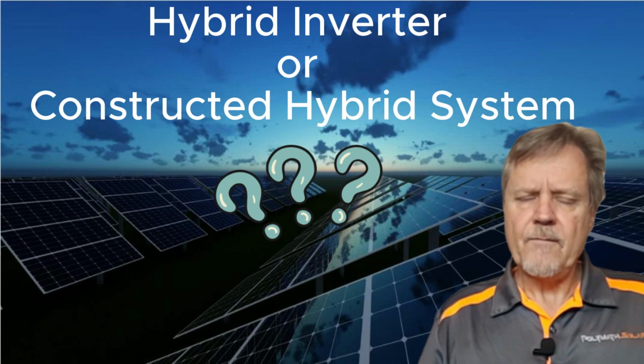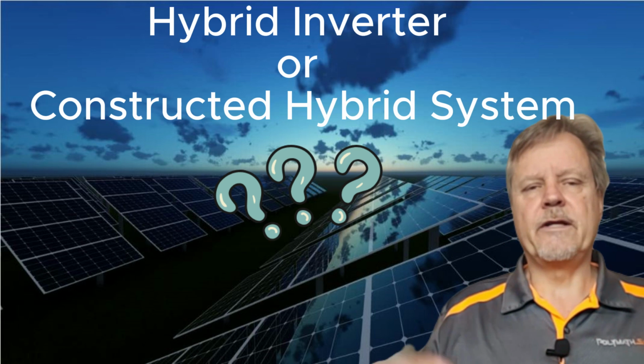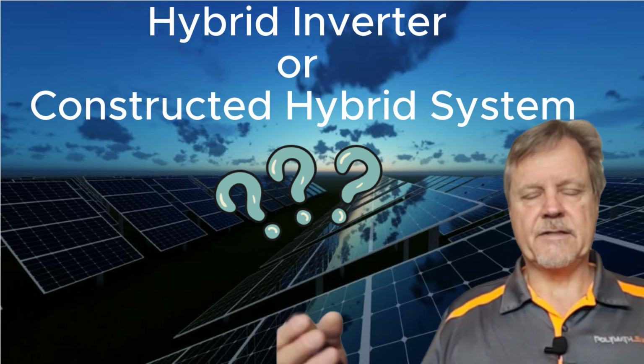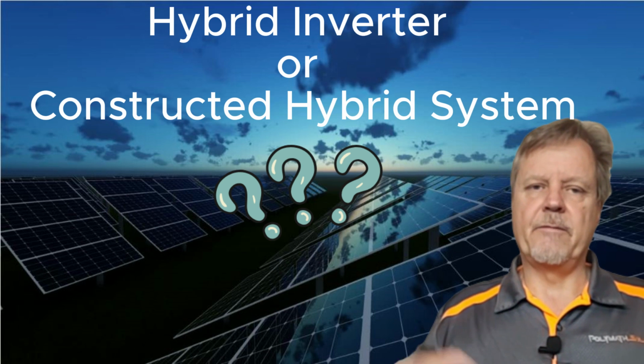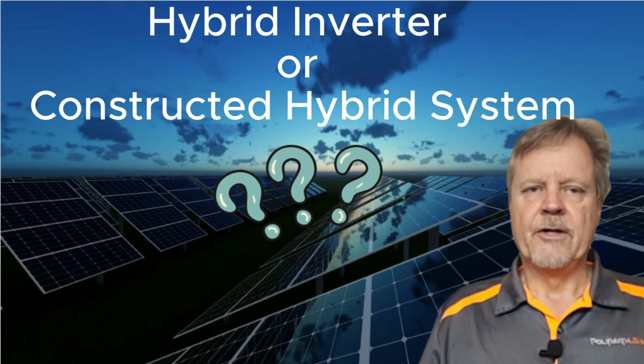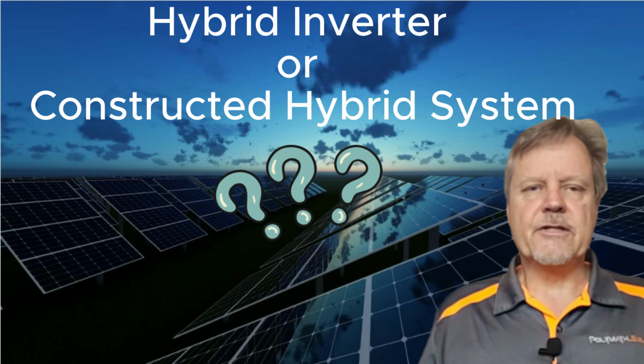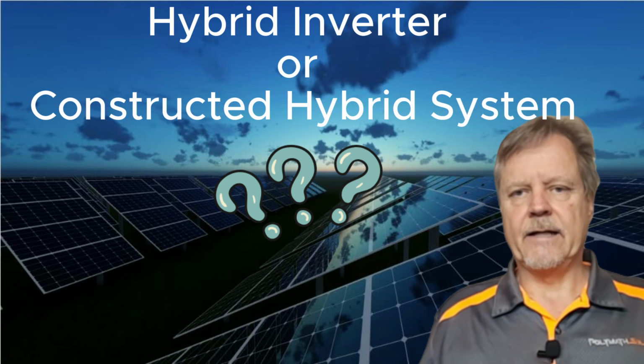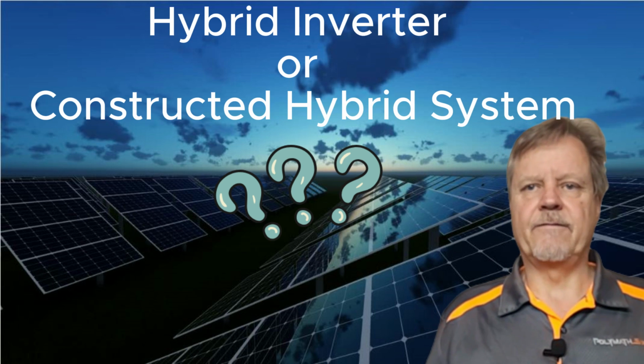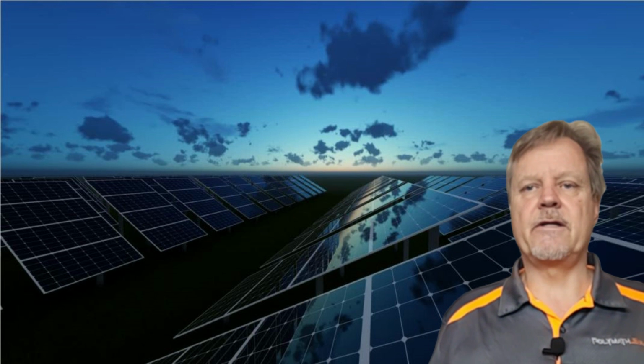Or if the battery inverter charger fails, if you had an AC coupled system, you still have the solar panels, and they can still be saving you money. So with a constructed hybrid system, you just have a bit more flexibility, and you don't have that single point of failure. Right, now let's talk about the inverter power rating.